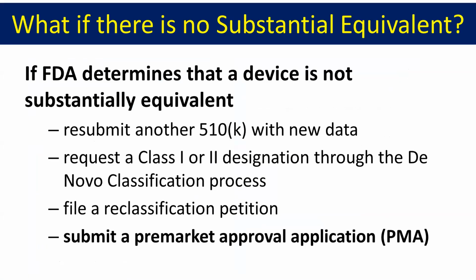And so for any device, they have to have this letter on file and publicly available. If there's no substantial equivalent, then you need to take another track. So a predicate device doesn't have to be identical. You can try resubmitting another 510K with new data. You can request a class 1 or class 2 designation through that de novo process. Or you might have to go ahead and submit a PMA.